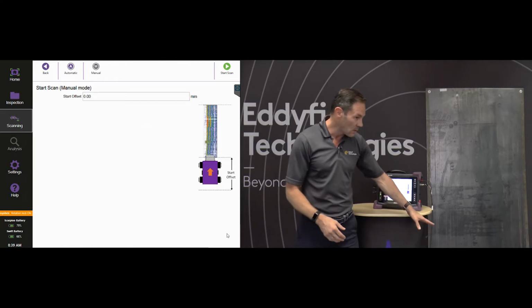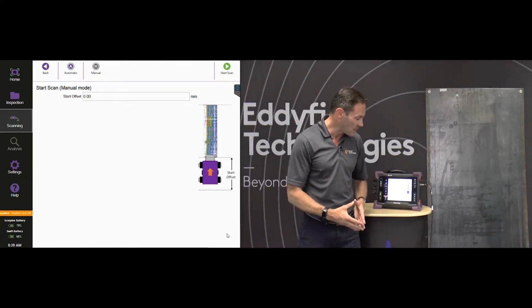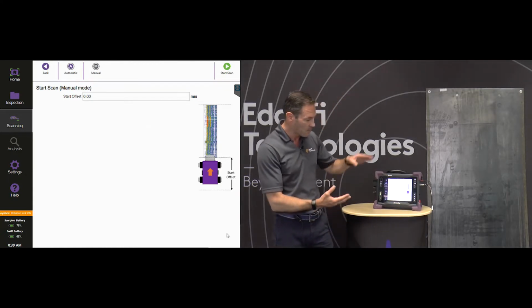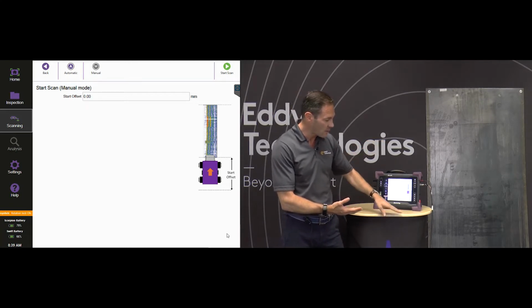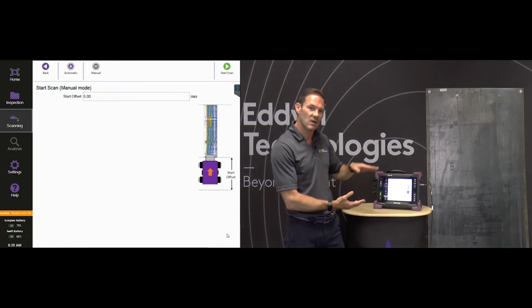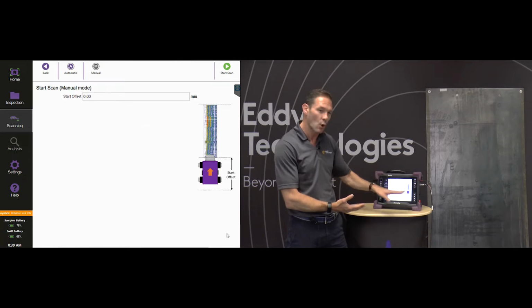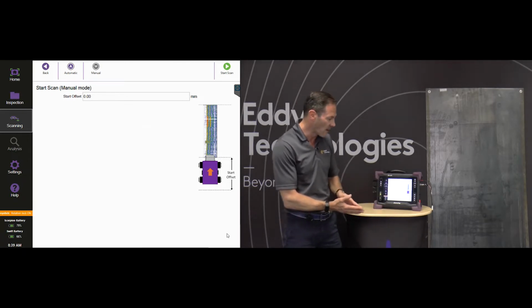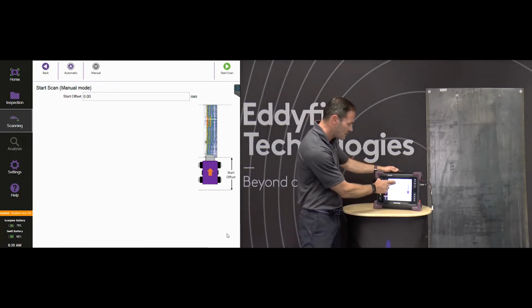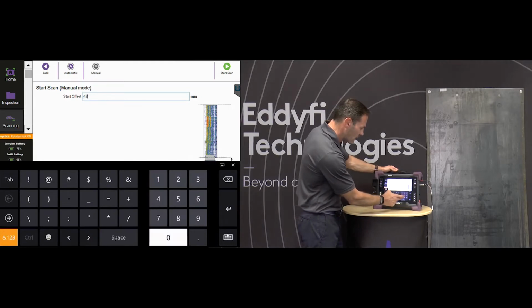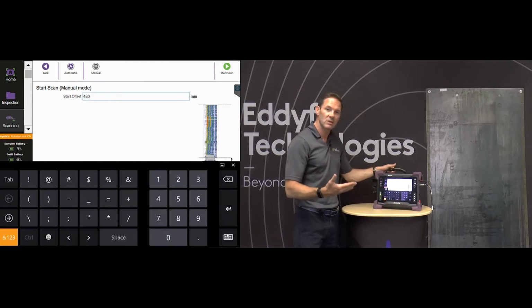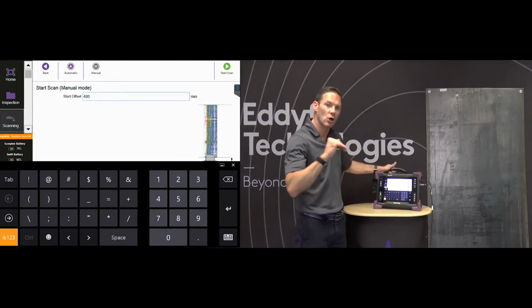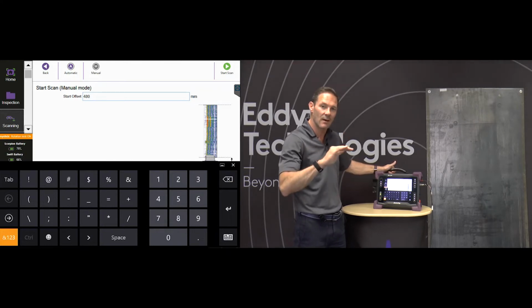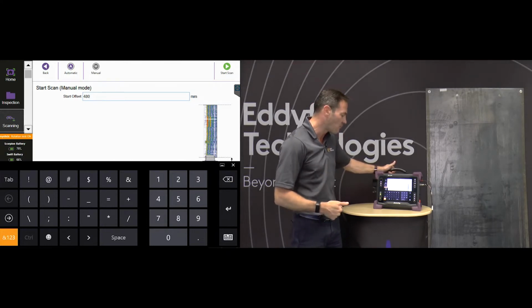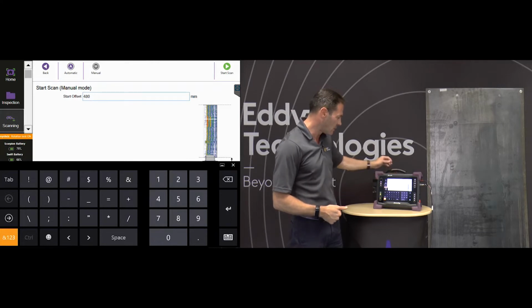As you can see, the scanner is at the bottom position of the tank, but for the first 480 millimeters we're not capturing any data because that probe is not really down at floor level. So we have to enter that distance where we're not measuring any data. The reason you'd do this is to make your life easier when aligning the data, if you use a program like CMap for easy reporting and configuration.